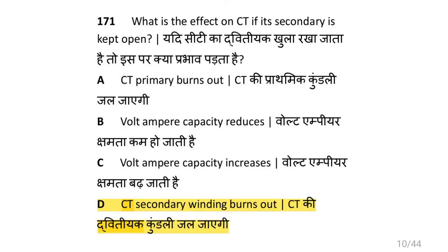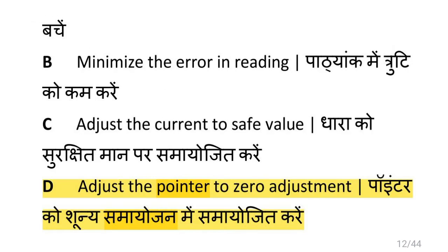What is the effect on CT if its secondary winding is kept open? Then the CT secondary winding burns out due to enormous heat. What is the purpose of the variable resistor connected across the shunt type ohmmeter? That is to adjust the pointer to zero adjustment.